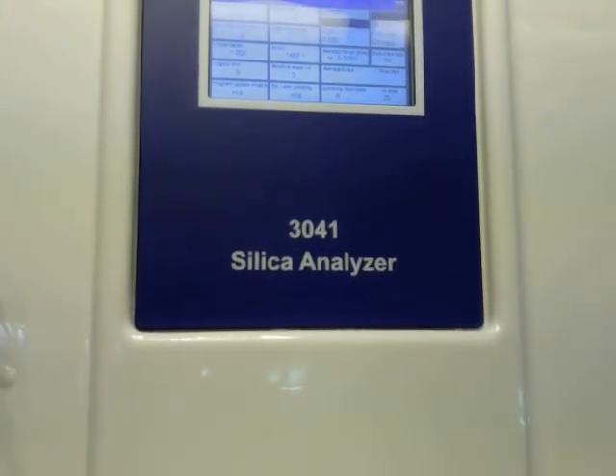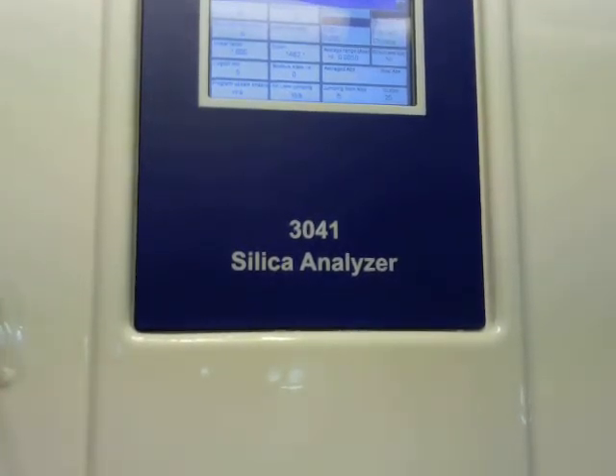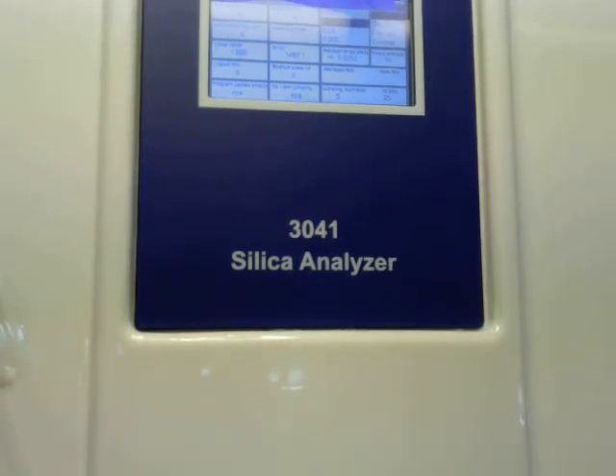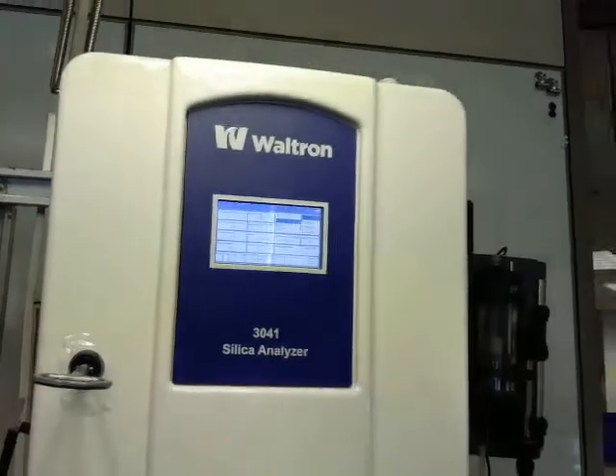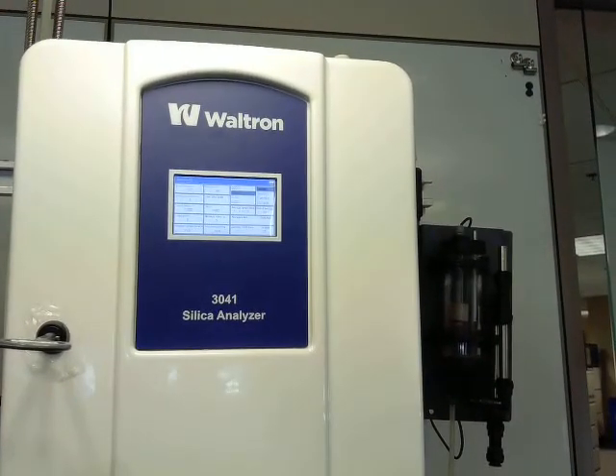But obviously, what we've found more often happens is people walk by the analyzer and assume that it's powered off. So if you don't want to see that, and you always want to see the screen online to assume that your analyzer is running and see your reading, you set that number to 0, and that way your screen will always be on. And worrying about the screen burning out doesn't really seem to be an issue. We've had a couple of these that have been installed now for over 10 years and hadn't had to replace any screens due to the backlight burning out or anything like that. So again, if you put the analyzer on, walk away from it, and then you come back a few minutes later and it looks like it's off, could just be the backlight timer.